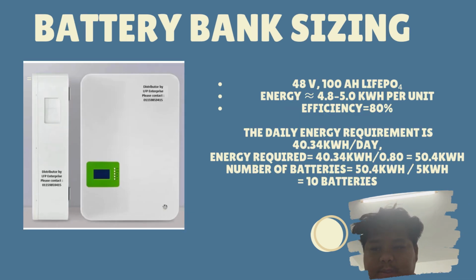For battery bank sizing, we are using a lithium iron phosphate battery with the following specifications: 48 volts, 100 Ah, energy of 4.8 to 5.0 kWh per unit, and efficiency of 80%. The daily energy requirement that we calculated earlier is 40.34 kilowatt hours per day. We divide the daily energy requirement by the efficiency, which gives 50.4 kilowatt hours. The number of batteries is 50.4 kilowatt hours divided by the energy per unit, 5 kilowatt hours, resulting in 10 batteries.